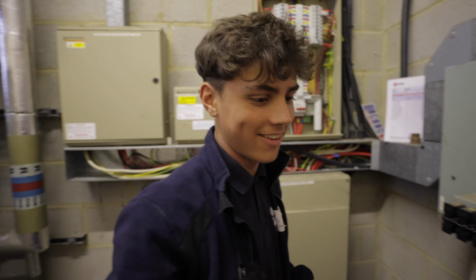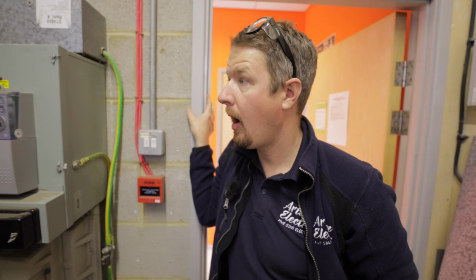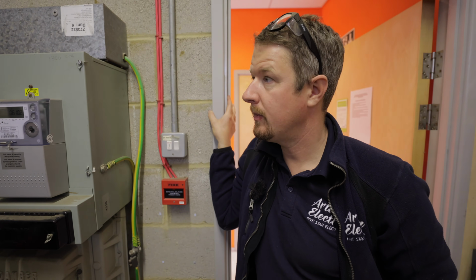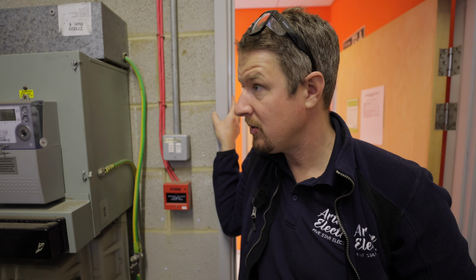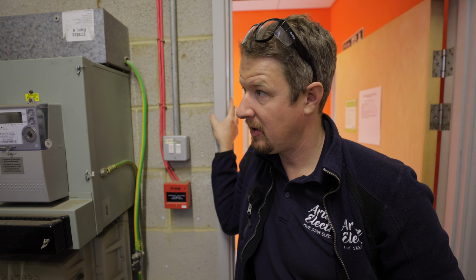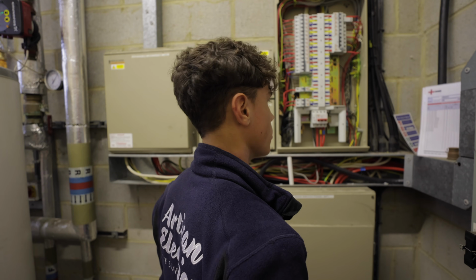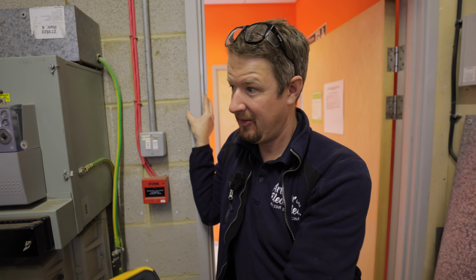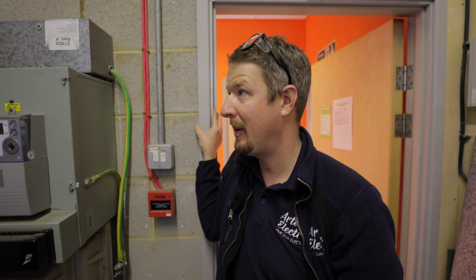By using that, well you can do it on a known good supply. Now you could do it on the main switch. What is the disadvantage of doing it on the main switch? I'm not sure. Well, there's no circuit protection other than a massive 100 amp MCCB, so if you did slip and make a little mistake, you've got 100 amps - it's going to go big, it's going to go bang, big style.